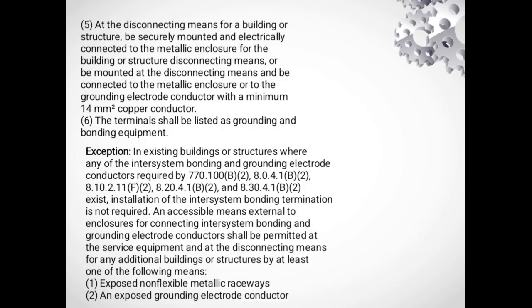Number 6. The terminal shall be listed as grounding and bonding equipment. Exception. In existing buildings or structures where any of the inter-system bonding and grounding electrode conductors required by 770.100(B), 8.0.4.1, 8.10.2.11, 8.20.4.1 and 8.30.4.1 exist, installation of the inter-system bonding termination is not required.